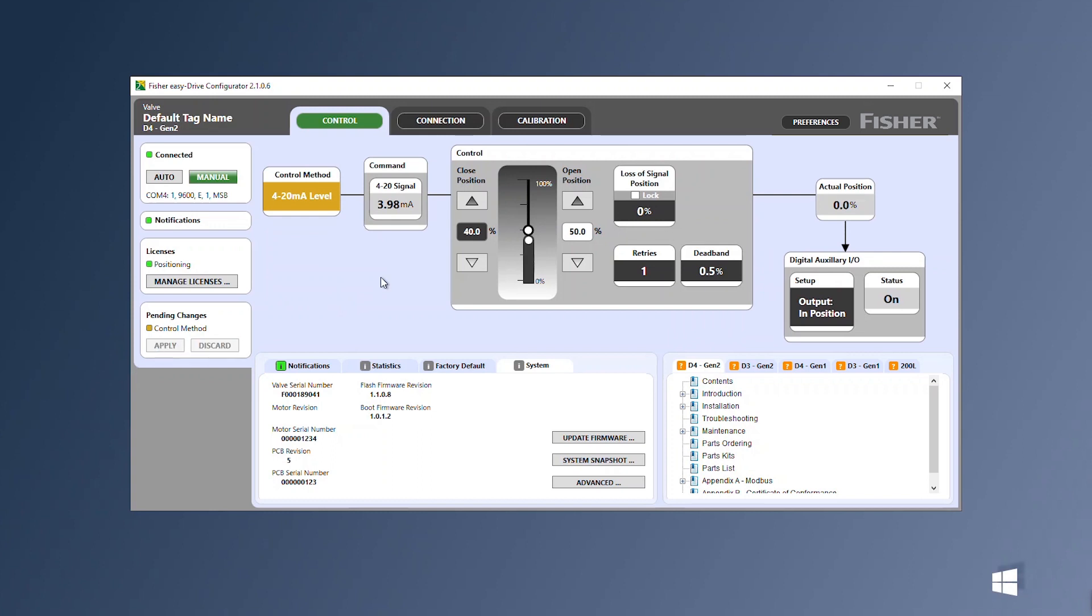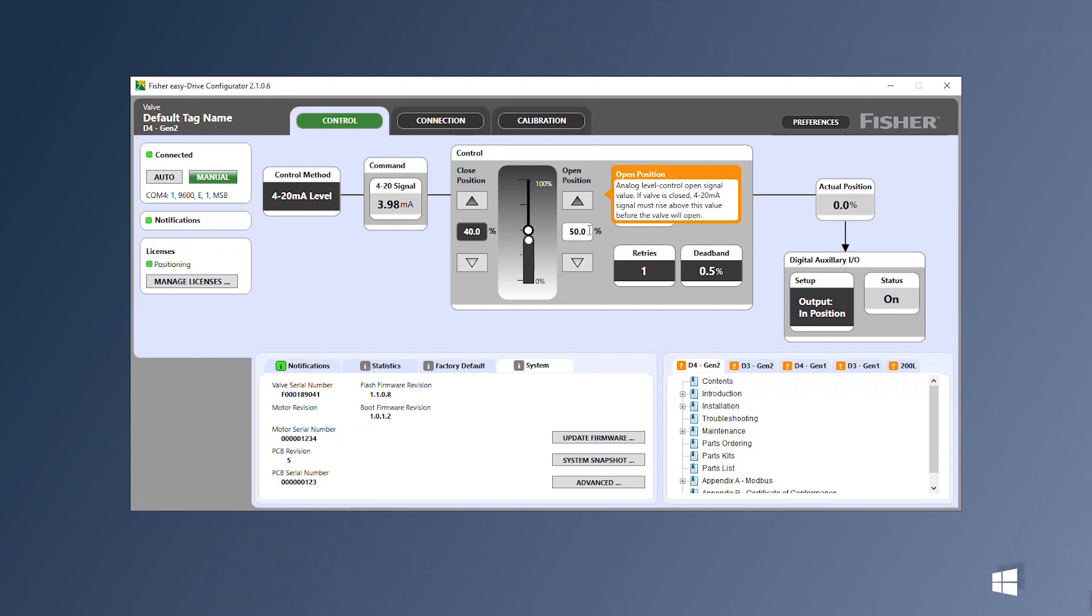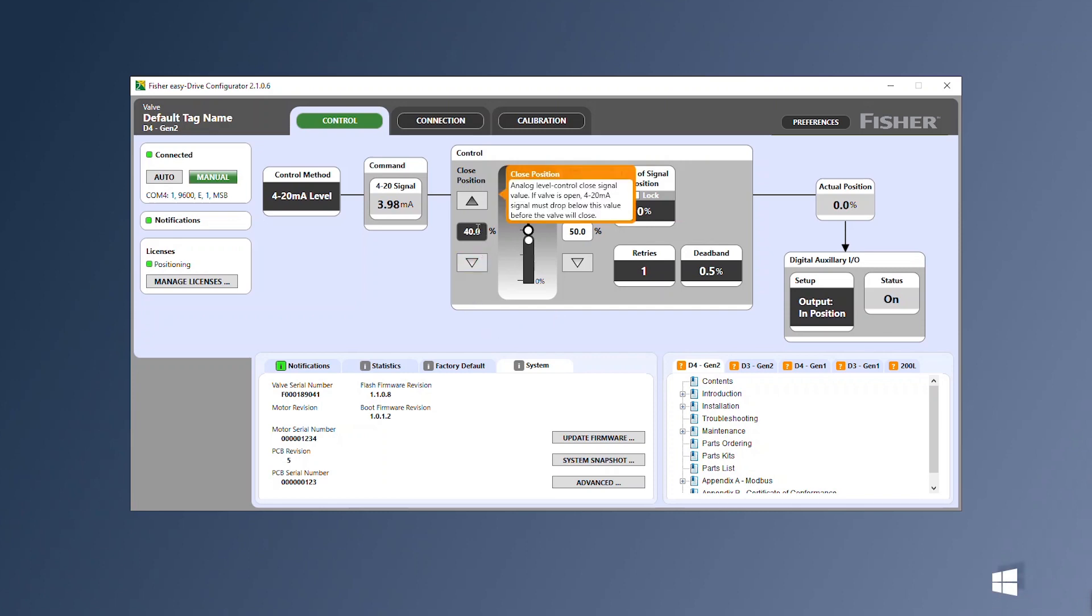The Gen 2 Easy Drive controller has a mode specifically created for heater-treater level applications where the transmitter is connected directly to the valve. It allows different open and close points to be configured.